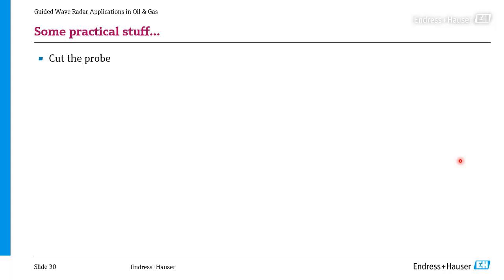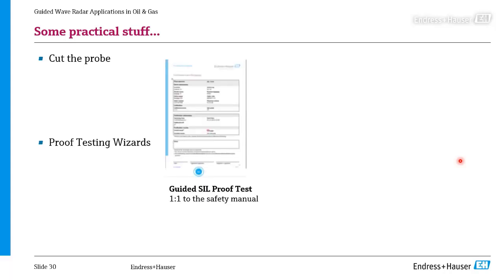Our devices from Endress+Hauser also have wizards built in, for commissioning but also for proof testing. This makes your life easier because you'll be guided through a proof test, one-to-one with the safety manual, so it's a complete and correct proof test. It will guide you and you'll also get documentation, which might save you time in your daily work or maintenance schedules.